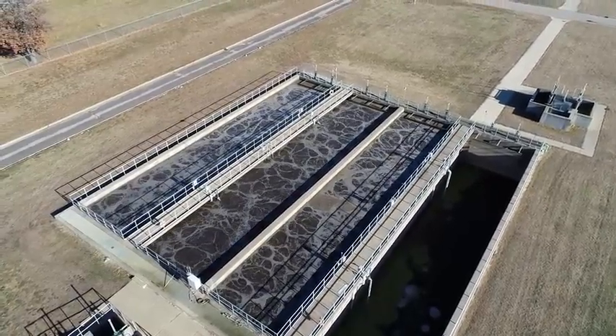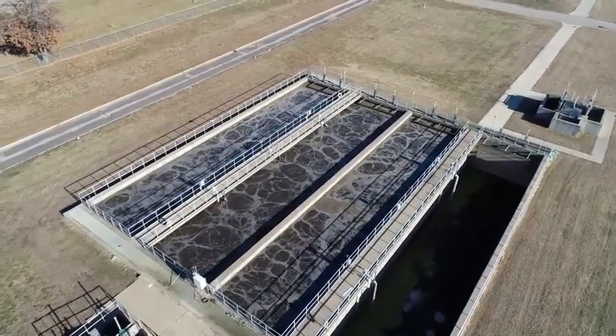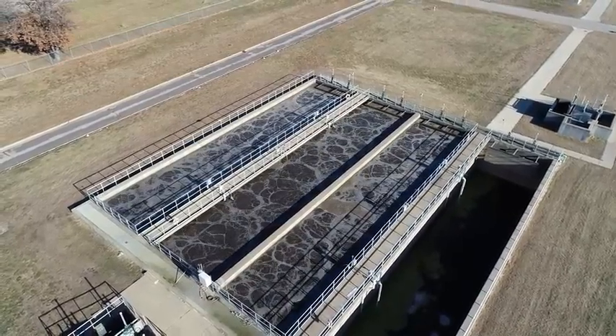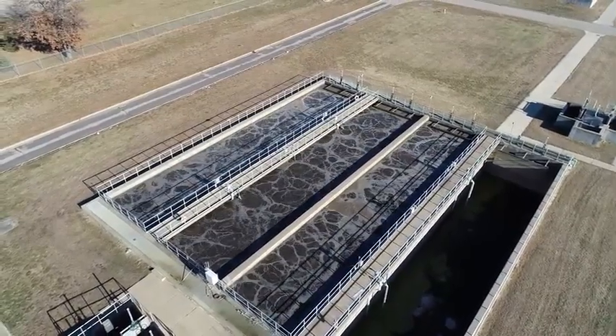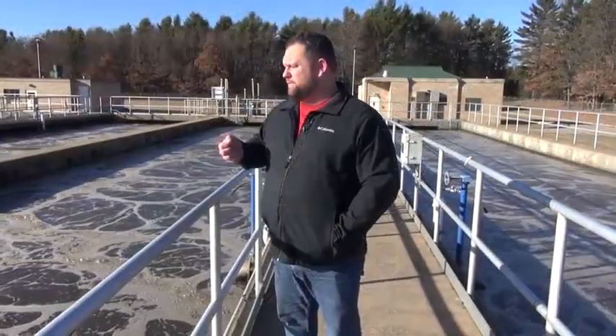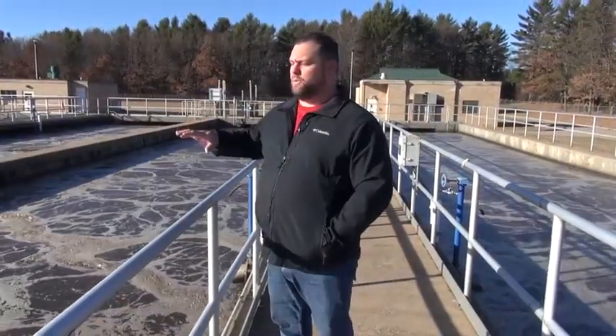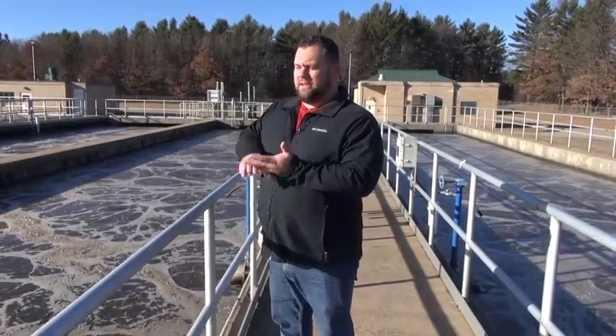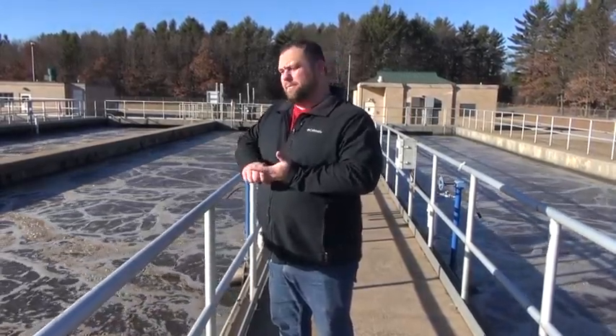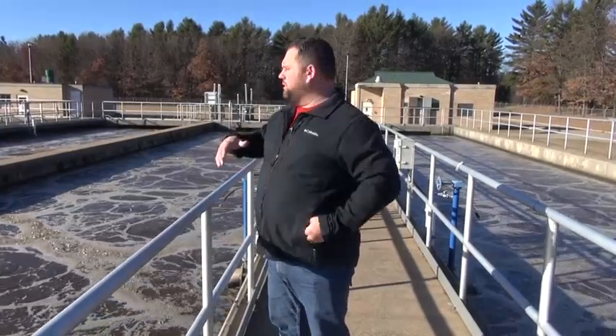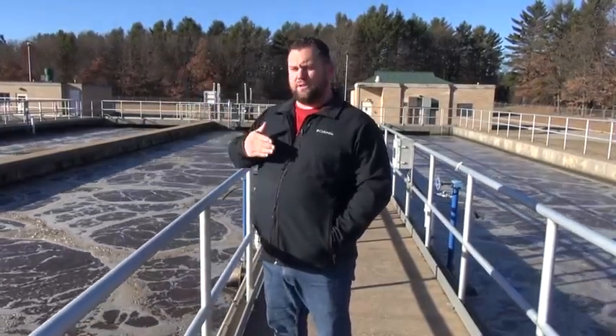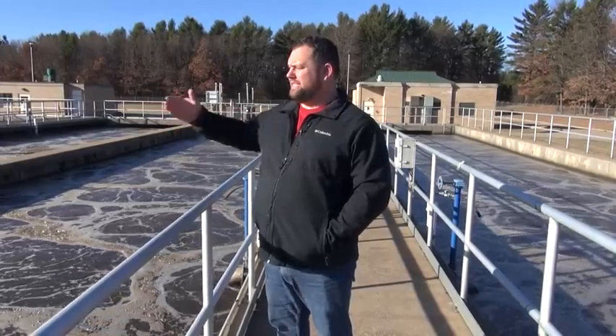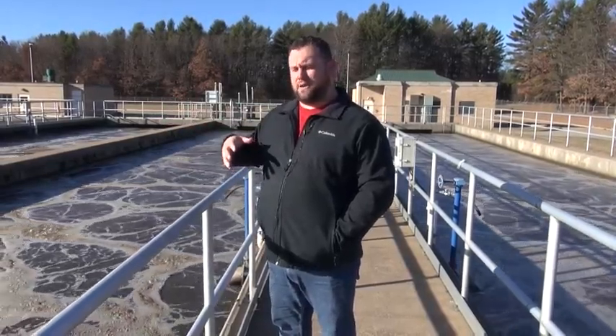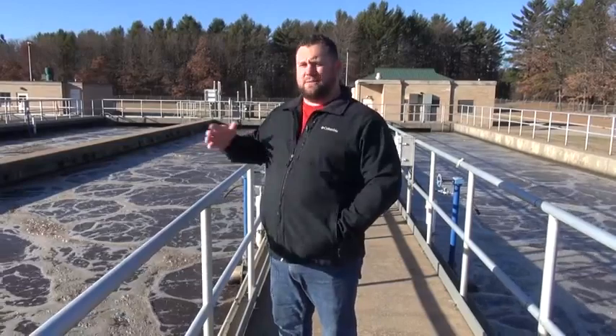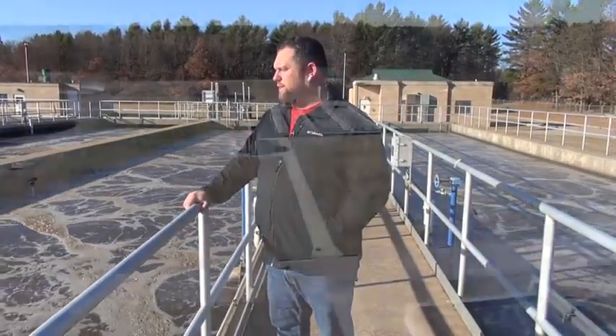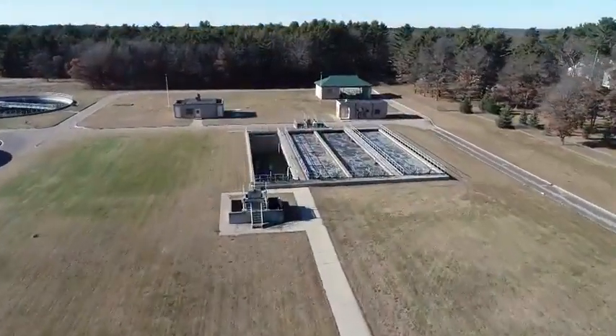This facility, we do have an ammonia permit, a nitrogen permit. So you need longer cell retention times to fully nitrify, to use up nitrogen as ammonia. So this stage really allows us to make sure we're removing 99% of the ammonia, 99% of the BOD, and 90+% of the phosphorus. So it's just another way, and we have the ability here, there's 4 chambers, 4 aeration basins. We have 3 on it this time. We could go down to 2 if we didn't need all the treatment capacity. We could go down to 1. A lot of flexibility down here, just to make sure we're achieving all of the treatment needs that we have.